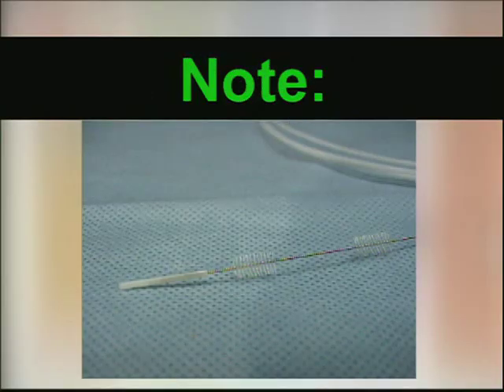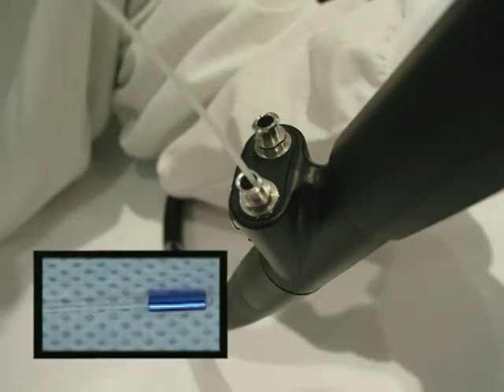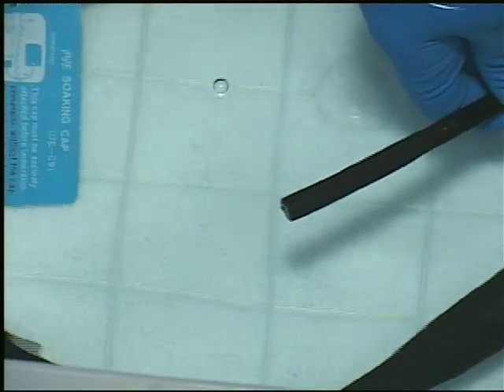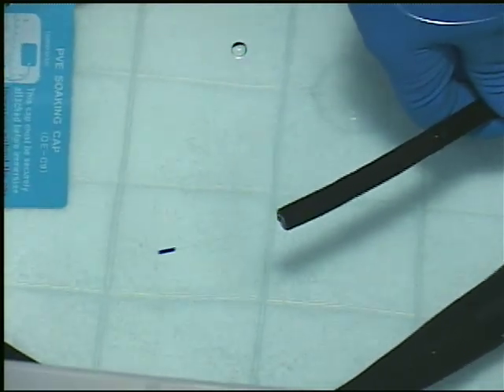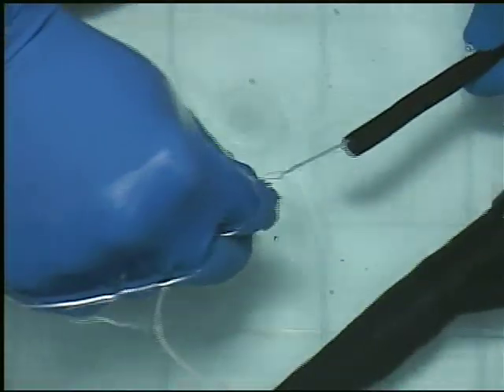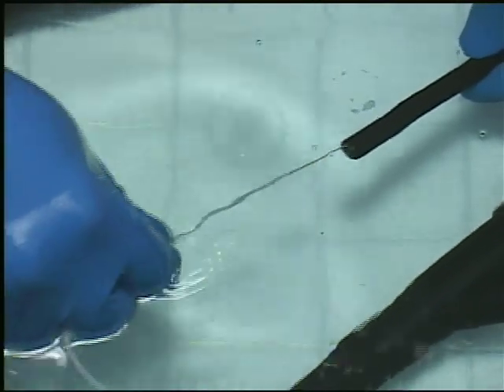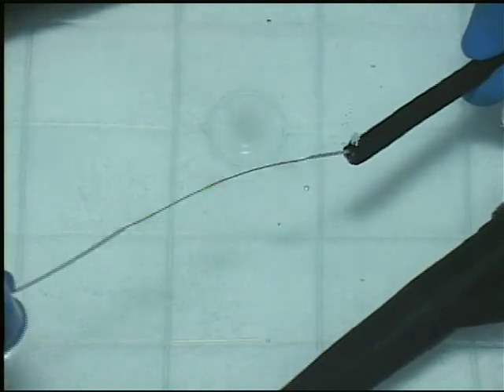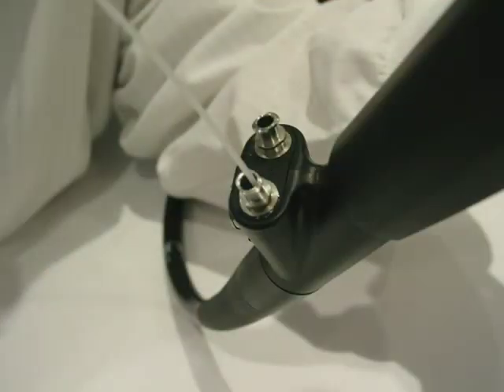Note: when using the tri-bristled cleaning brush CS6021T, slowly remove it from the endoscope, being careful not to fling patient debris or contaminants into the air as the bristles exit the scope. Insert the blue-coated end of the CS6021T cleaning brush into the instrument channel inlet and gently advance until it exits the scope distal tip. Grasp the back end of the brush shaft and gently pull the brush from the scope distal tip. Repeat as necessary until the brush is visibly clean. Repeat this brushing procedure on the second instrument suction channel.